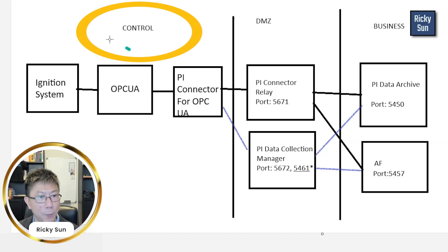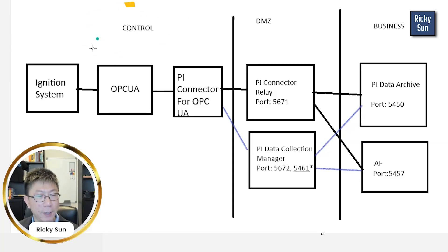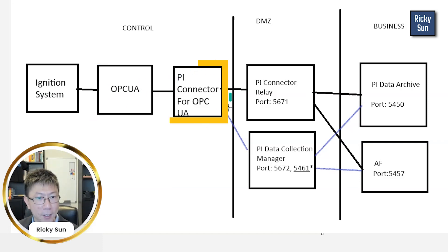If you look at my screen, I have a control network here. In my control network, I have my Ignition system with OPC UA, and I'm going to install PI connector for OPC UA inside the control network. After I did that, I was able to connect to the OPC UA source by specifying the path of OPC.TCP — that kind of thing — to get it set up.